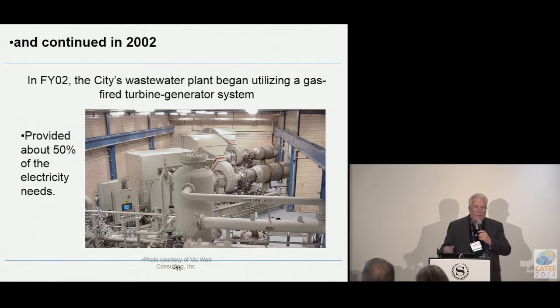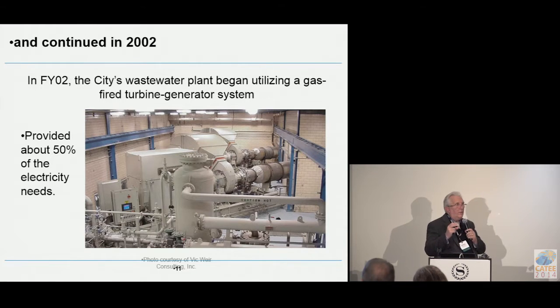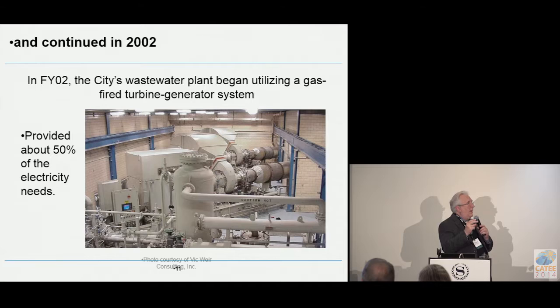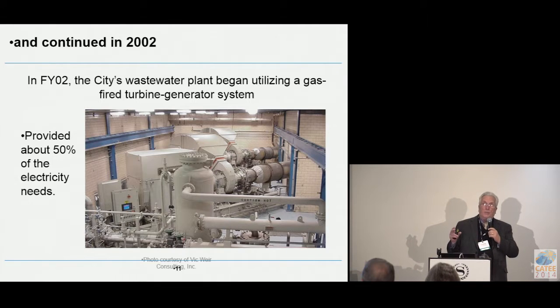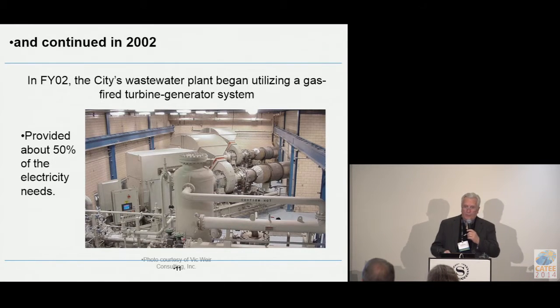Turbines are effective as long as you use them at their maximum load. If you go down to 30%, it isn't as effective. So what we did was power up one completely, and used the other as backup or as a demand-type source.